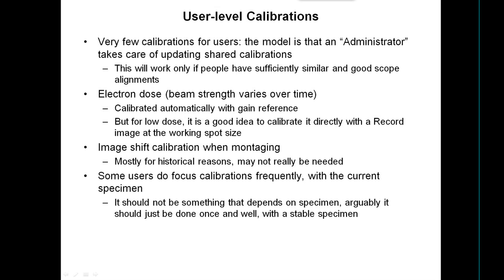Electron dose is something users must calibrate themselves, because beam strength varies over the course of hours and certainly from day to day. It does get partially auto-calibrated with the gain reference, but once you get to a spot size far away from that, you're relying on an indirect chain of inferences to estimate the dose. So it's a good idea to do a direct calibration at your working spot size for low dose.